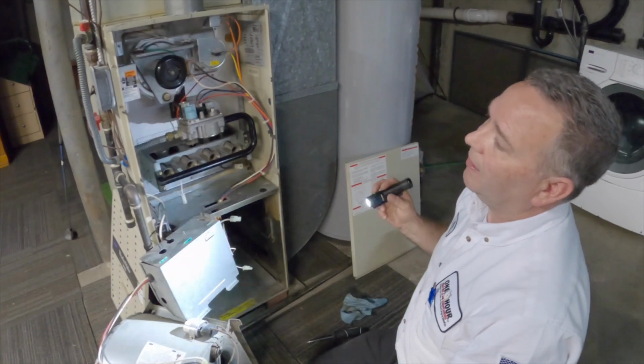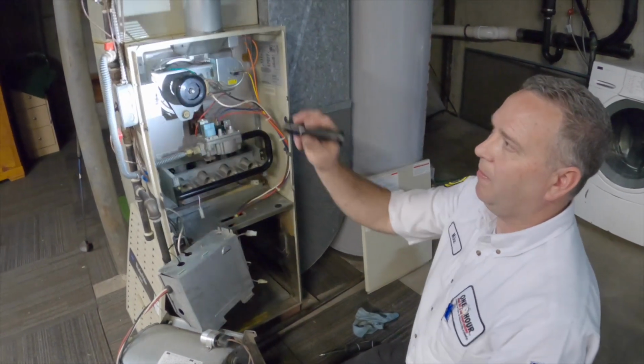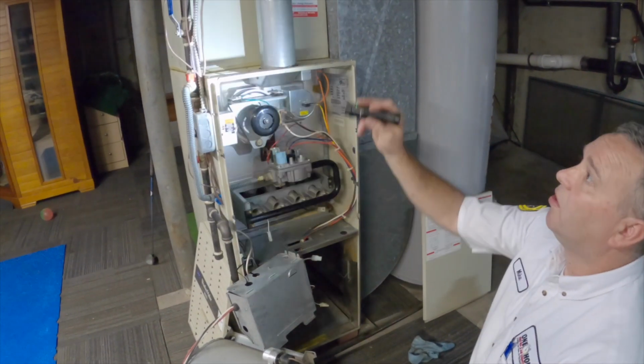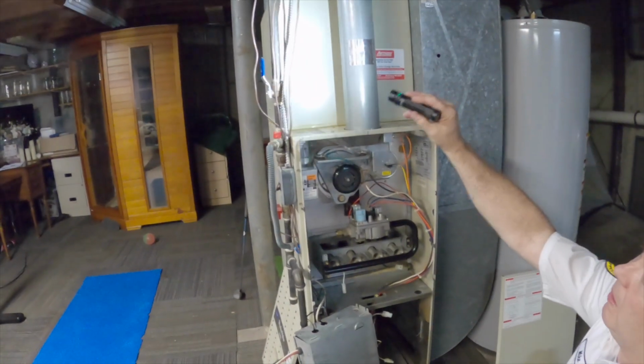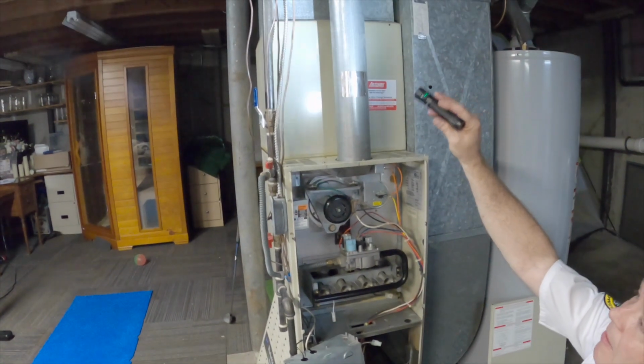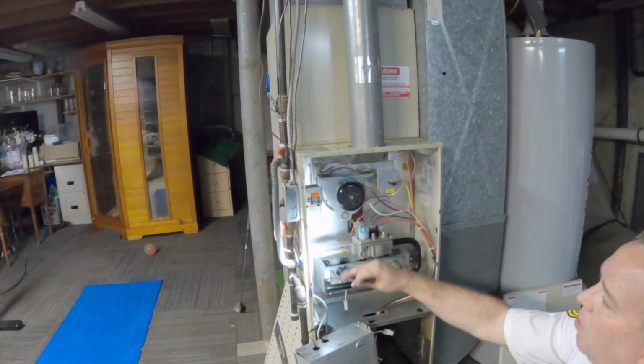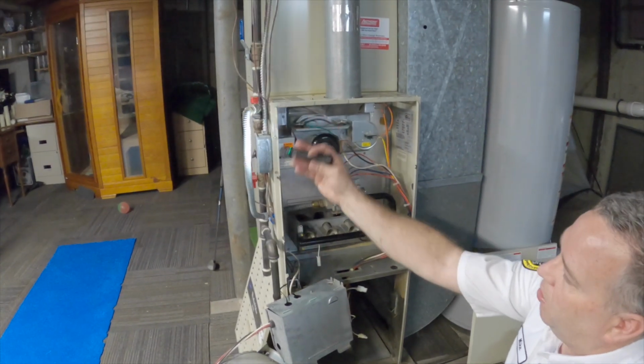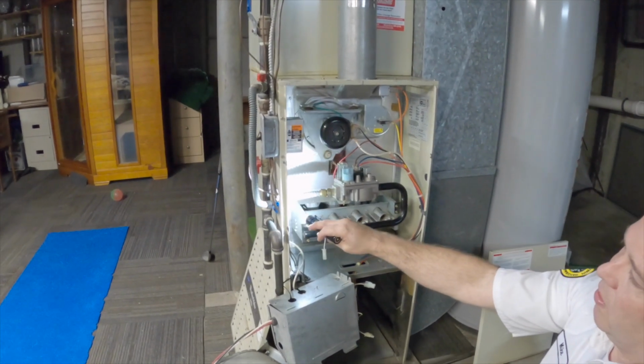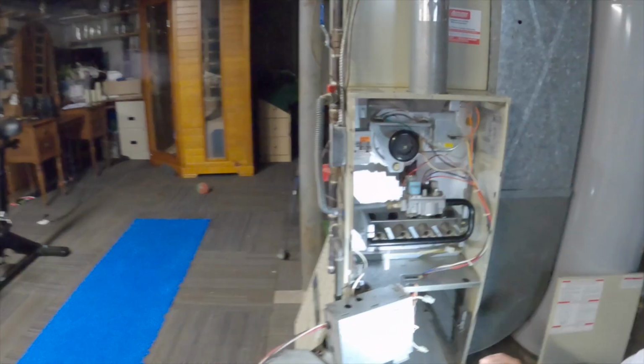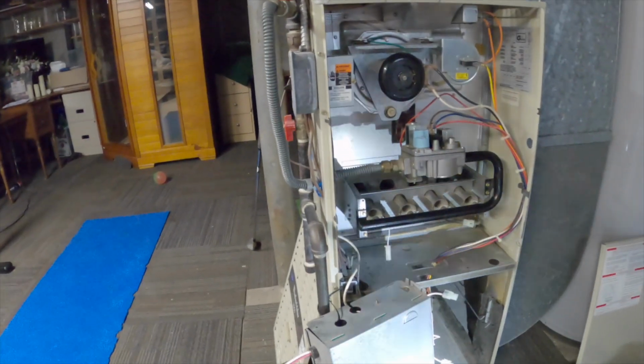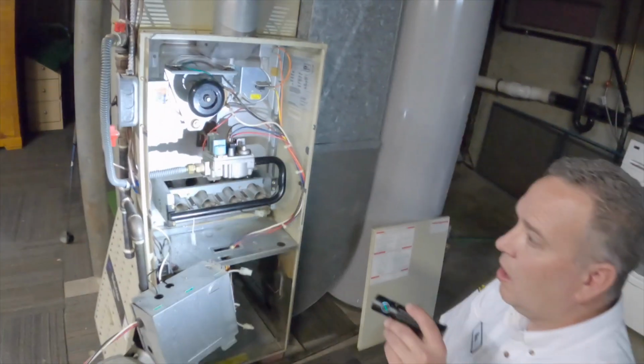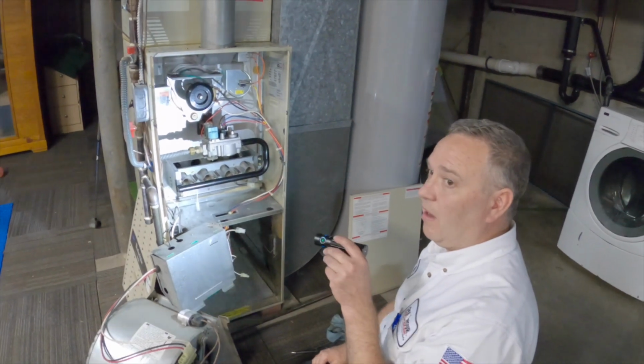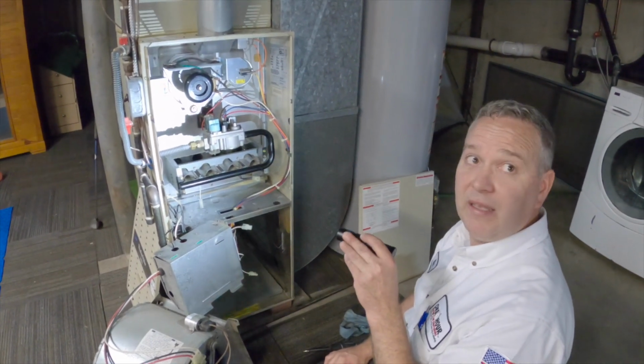This has flexible gas piping going through the furnace cabinet. So you see this main gas pipe coming in, that's your black pipe. It's against code to actually have your flexible gas piping going through the furnace cabinet, because what can happen, and the first time that I've seen it in the industry happened actually last year, and we just kind of lucked out that Jordan was there to do the maintenance and noticed it.